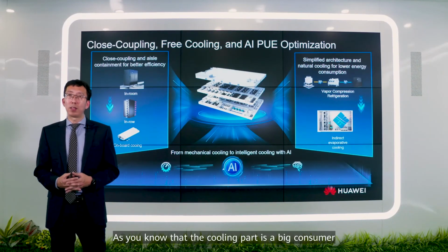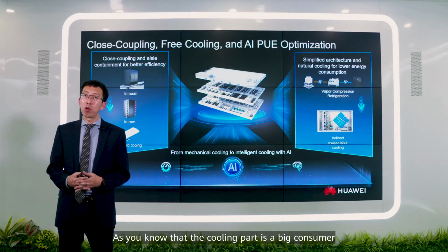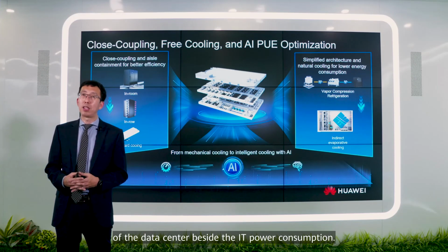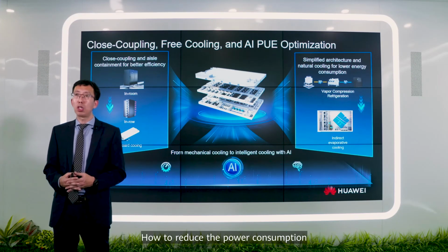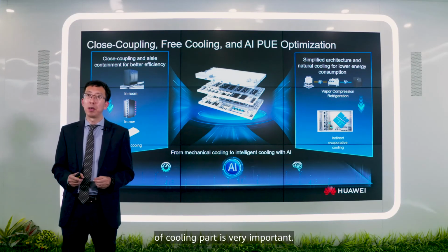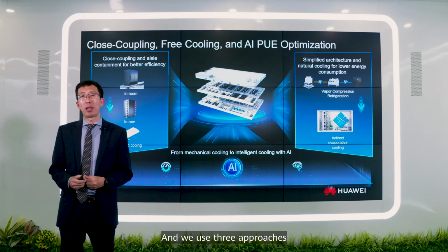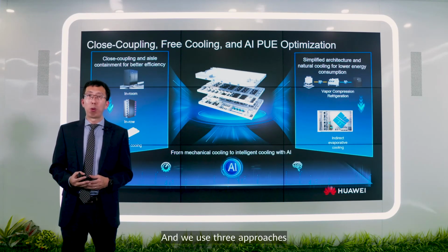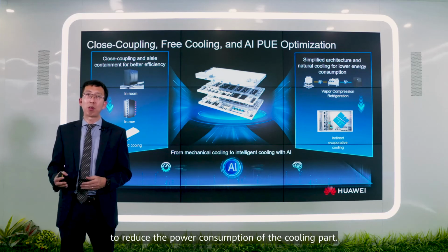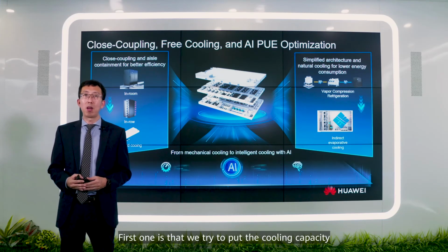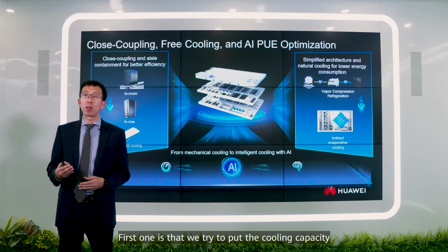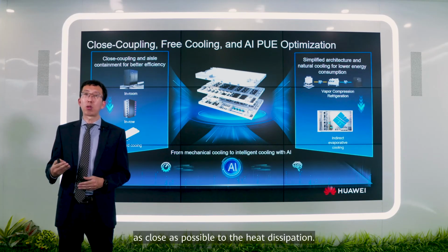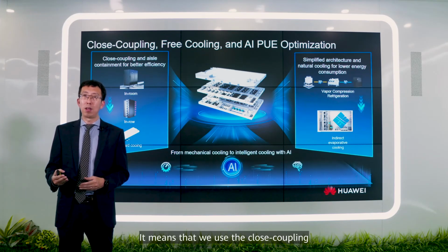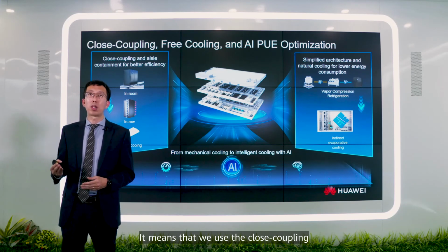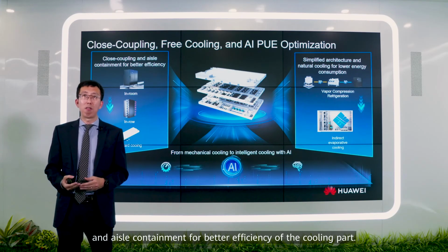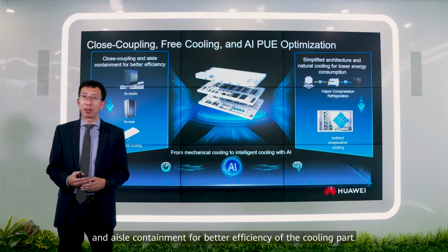The cooling part is a big power consumer of the data center besides IT power consumption, so reducing its power consumption is very important. We use three approaches. First, we place cooling capacity as close as possible to the heat dissipation, using close coupling and aisle containment for better cooling efficiency.